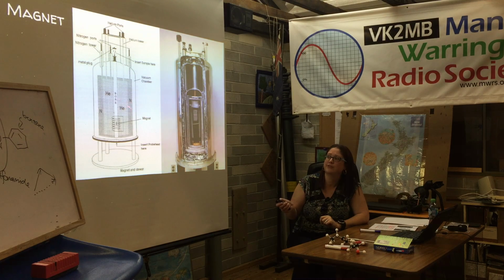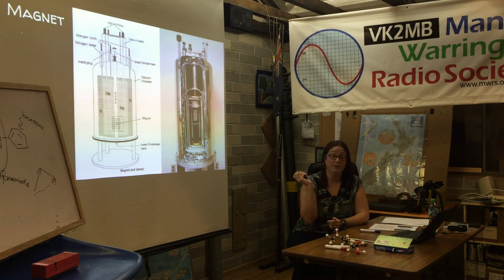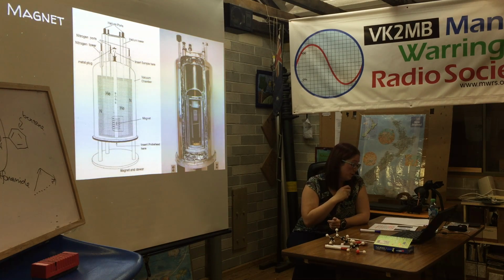If these levels fall beyond that critical point, or if someone accidentally brings a wrench too close to the magnet and you get a violent jolt, or something happens that upsets the superconducting nature of the solenoid, then you can get a quench, which we talked about before, and there's a video on the next slide which shows you what a quench is.